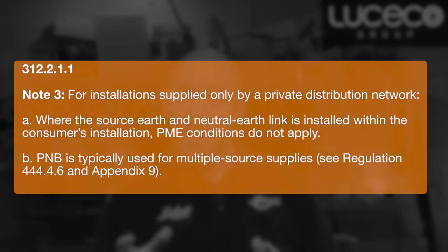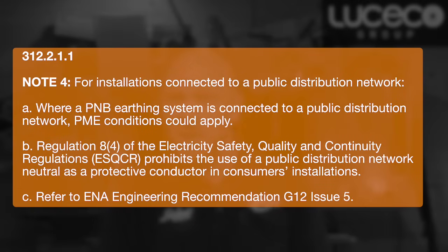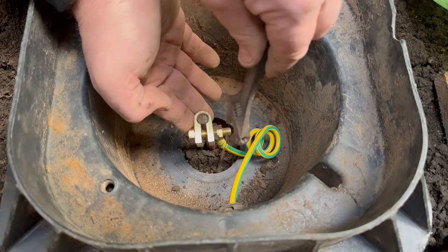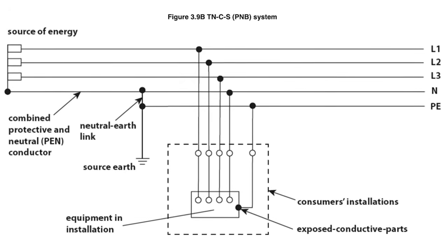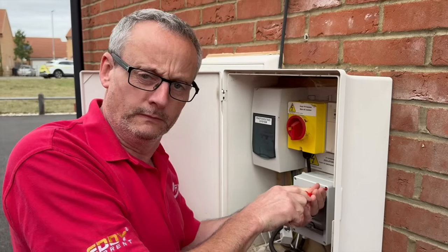There is also an important distinction to understand. Where a system is supplied by a private network, PME conditions do not apply even if the arrangement looks similar. And where it is connected to a public network, the regulations prohibit the use of the neutral as a protective conductor within the installation, so you cannot assume it behaves in the same way as a TN-C-S system. So the change here is not that PNB is new, it is that it is now formally recognised, and you are expected to understand what type of supply arrangements are connected when you come across it.